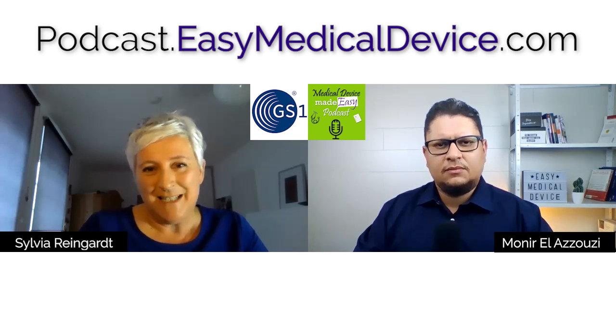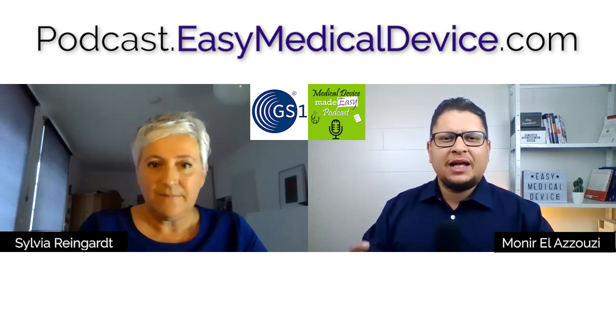It's covered by our license package, because in total we have 12 GS1 identifiers. We just talked about the Global Trade Item Number, GTIN, and you can use that for the UDI-DI. And the second one you need for UDI in Europe is the Global Model Number, to fulfill the basic UDI-DI requirements. So the basic UDI-DI is a number that can group many devices under it. It's not one basic UDI-DI for one product. It's one basic UDI-DI for a group of products.